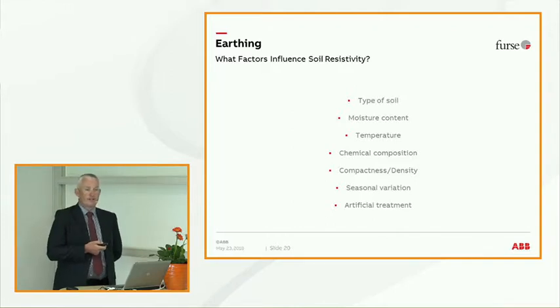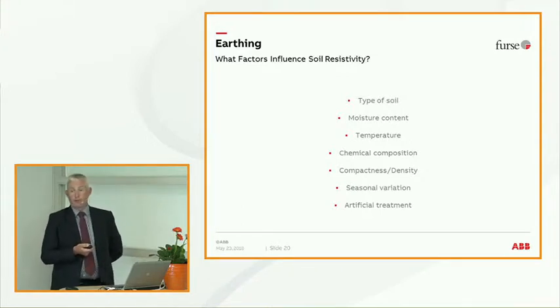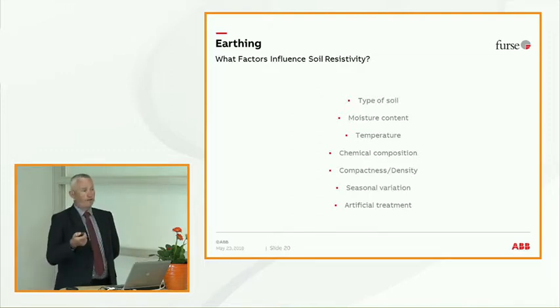When it comes to soil resistivity, you can do the soil resistance testing, but like I say, the type of soil matters. The moisture content: obviously if it's wet, it's a better conductor. This has to be taken into consideration when designing an earthing system. The temperature depends on the time of year. Certain regions, like this region, can have highs of 30 and lows of minus 30, so these have all got to be considered when doing the earth resistance. The compactness and density: if it's compacted and tight, it's going to be a better conductor. If you've got a lot of air gaps, it's not going to be as good a conductor. All these are considered.